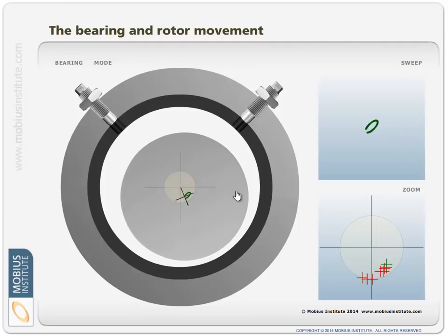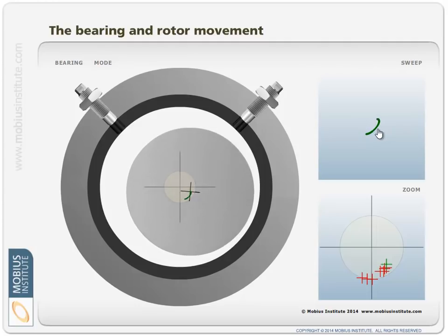So this is very important. As the machine's running up, I watch the orbit to see what's going on. I actually watch the orbit for each of our sets of prox probes, and I watch the centerline plot, and I make sure as I go through critical speeds what's happening, where is it sitting within the bearing, how's my alignment, how's my preload, how's everything, have I got a bend. All sorts of things can be determined from these two pieces of information.